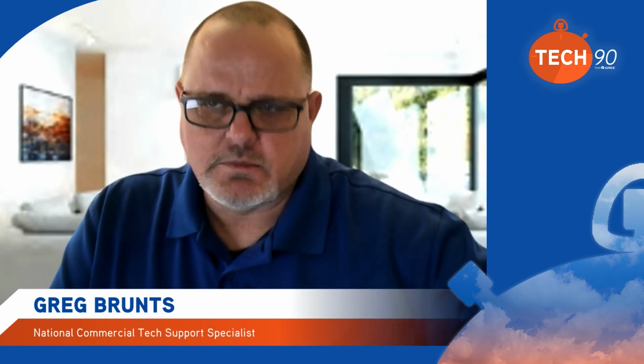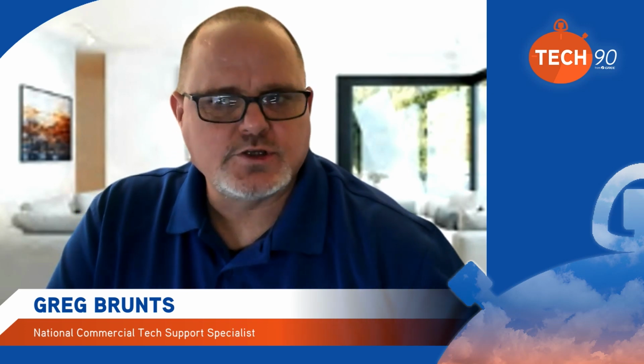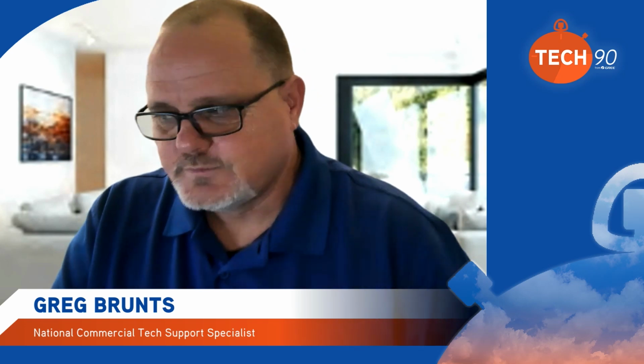If I set that at 60 minutes, that means I get a 60-minute runtime for that heat pump to catch up before it's ever going to let that electric heat come on. That's the idea behind it. So it's kind of dual purpose. We had the temperature differential in there, and James is the one who came up with the idea of putting the timer in behind it. I like the feature, and it makes sense, so I'm glad we added it. I just like to give the heat pump a chance to do its business.